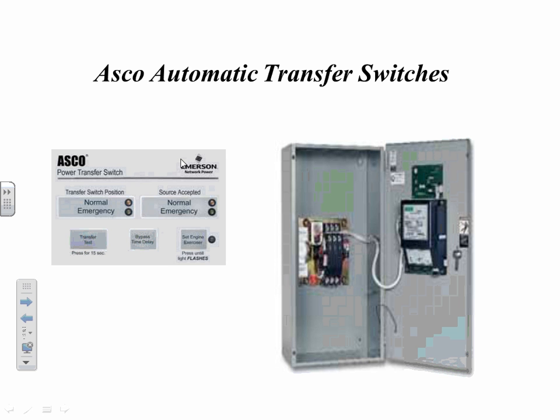When you walk by the transfer switch normally, you've got normal connected to the load. Both of these will be green. Exercise, these will be changing around. So we see the transfer switch in the normal position, green. When it transfers over to the generator, you'll see the transfer switch position for emergency light up red.